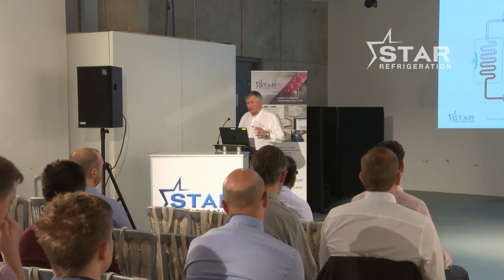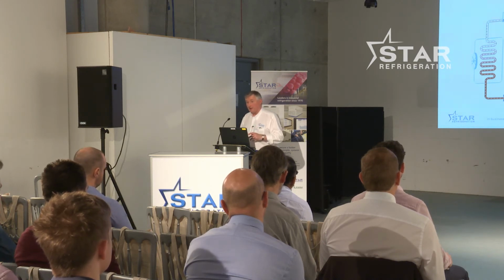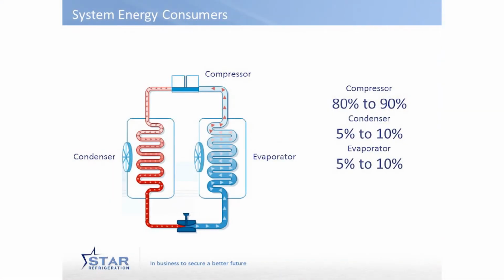The other major users, as was mentioned, are the condenser fans and pumps and the evaporator fans, and they would account for between 10 and 20% of the total. There might be other loads like glycol pumps and so on, but typically they'd be smaller. So we'll focus on the core of the refrigeration plant, and the things that will help move your energy consumption in the right direction. So the compressor, 90% maximum use. Condenser and evaporator, 5 to 10% of the energy use.